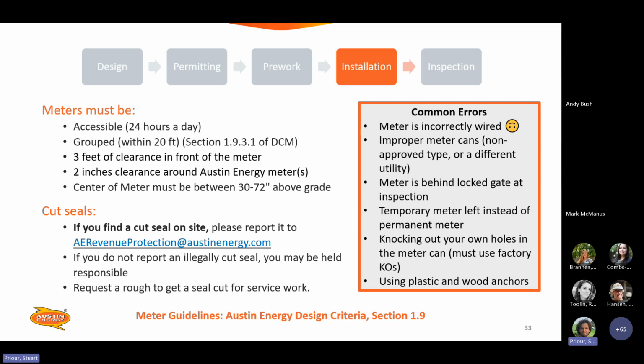Some common errors: the meter can is incorrectly wired. What that means is you've got your solar landing on the load side of your PV meter. Solar is going to land on the line side always. Basically line to line. It's a quick way to think about it. Line of your disconnect to line of your solar meter. Load side of your solar meter to your interconnection point. Improper meter cans. We've got a list of approved cans that you can find on the website.